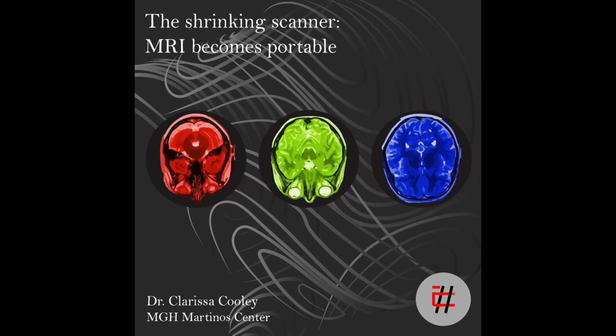To get more into the details now, what is the spatial resolution of the images acquired with this portable scanner, and what can you see and what can't you see? The image quality of conventional scanners is higher than with this scanner. The high field strength increases the signal to noise ratio, and therefore the resolution that you can achieve in a reasonable amount of time.